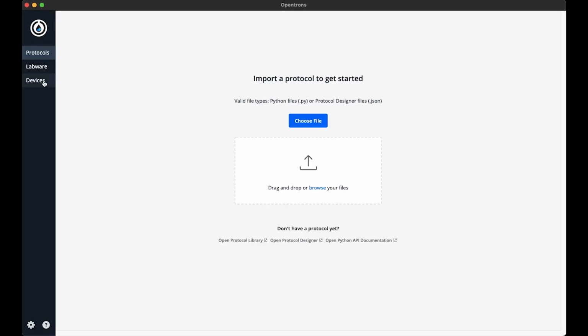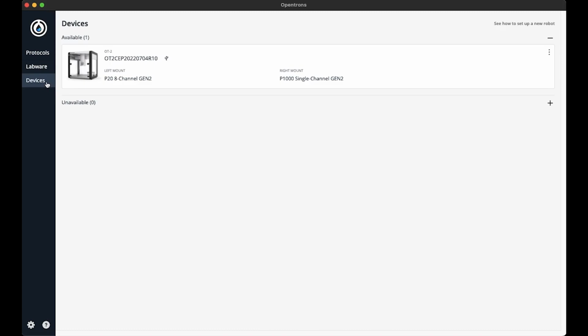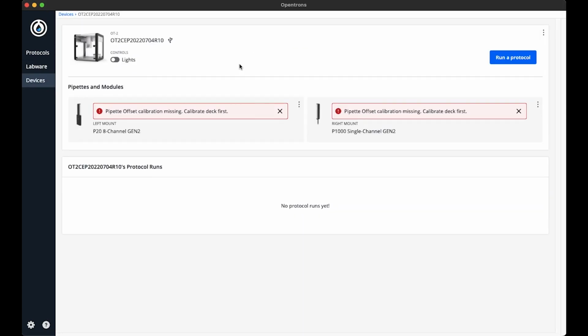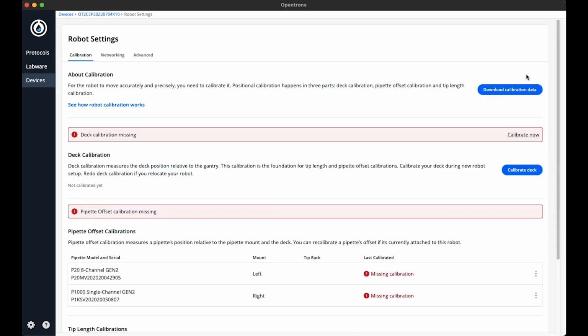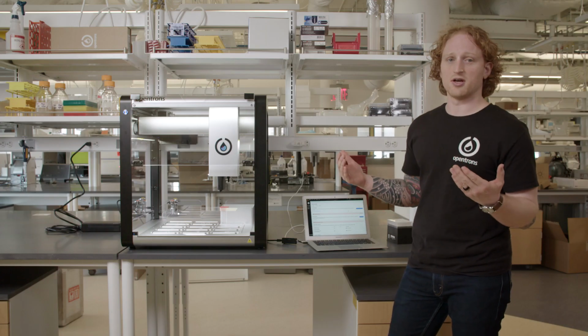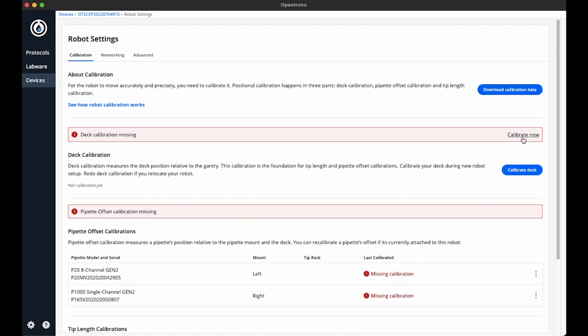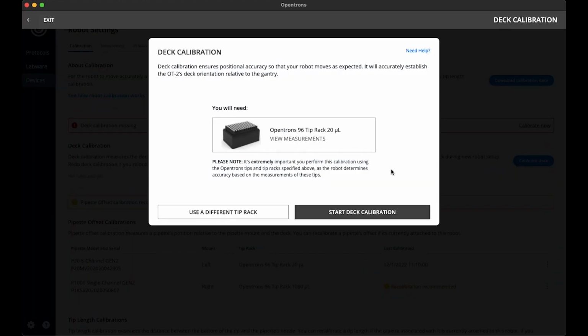To initiate deck calibration, I go to the Devices tab and click on the OT-2 I want to perform the calibration on. I then go to the 3-dot menu, Robot Settings. This Robot Settings page has all the information I need to know about the different calibrations on the OT-2. It says I am missing a deck calibration, which makes sense because this is a new robot. I will start deck calibration by pressing the Calibrate Deck button.